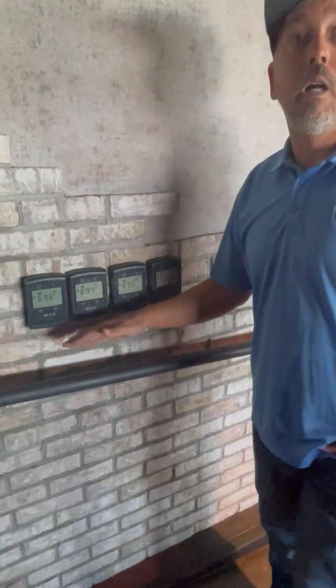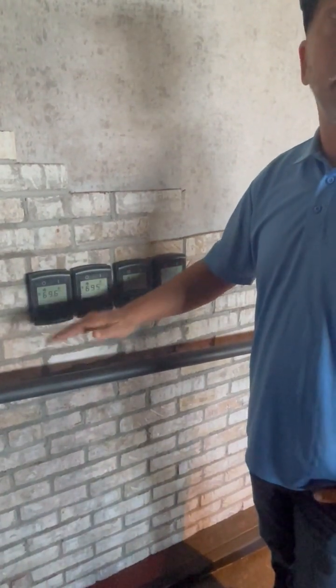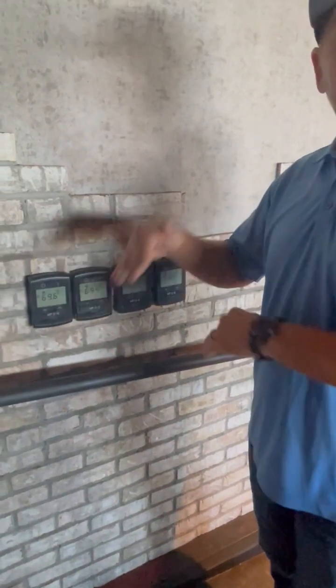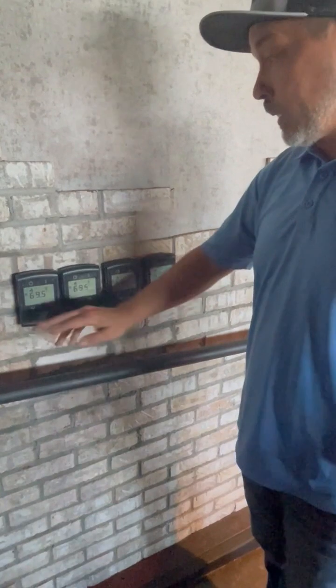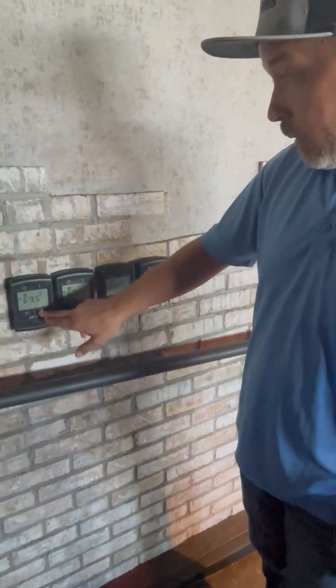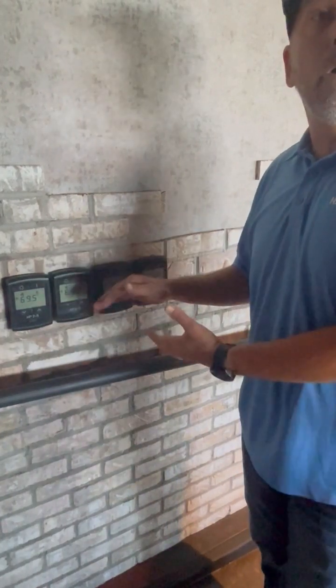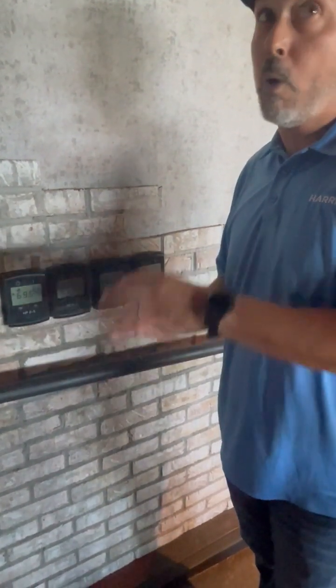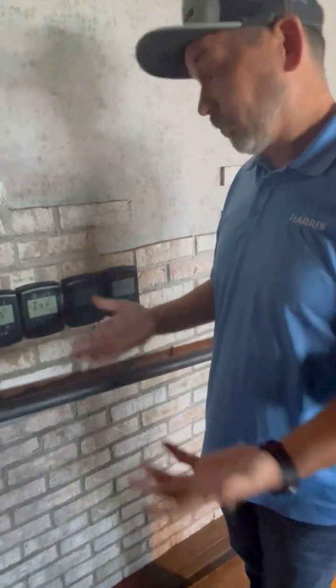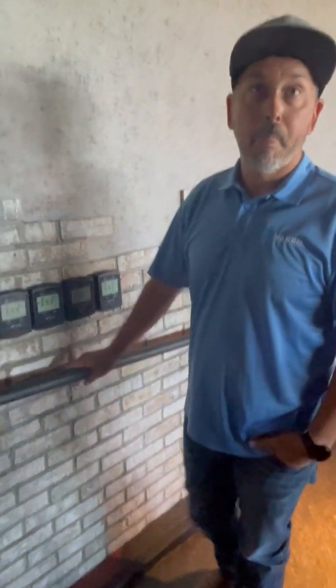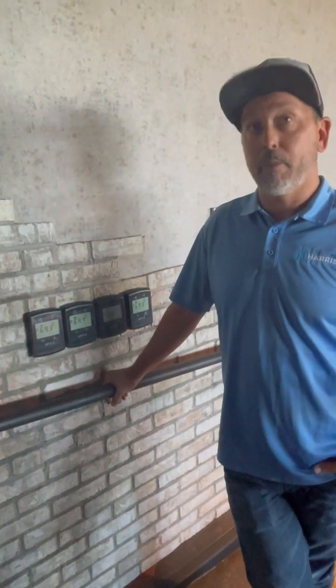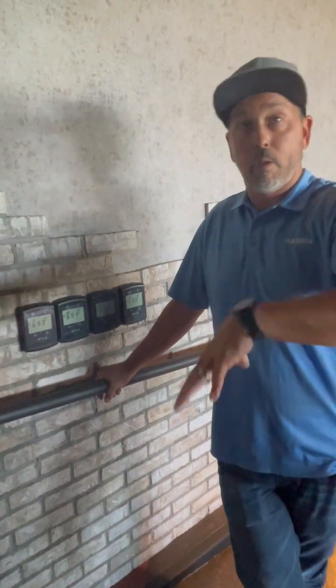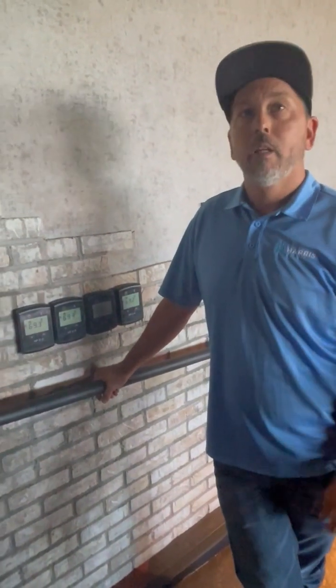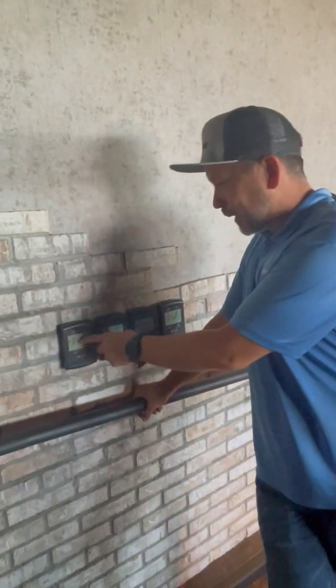The thermostats right here are, I hate to call them this, but they're dummy thermostats. The room temperature or space temperature is set on the front end, so these are non-adjustable - you can push the buttons all you want, but they won't move. They're here for display only. If supply temperature needs to be changed, raised, or lowered, it needs to be done on the front end. So if they want to adjust the temperature, they need to call facilities - that would be on whoever runs and operates the building. You cannot do this from this space; it's entirely for display purposes, just giving you the space temperature.